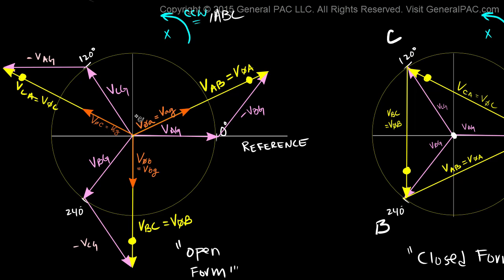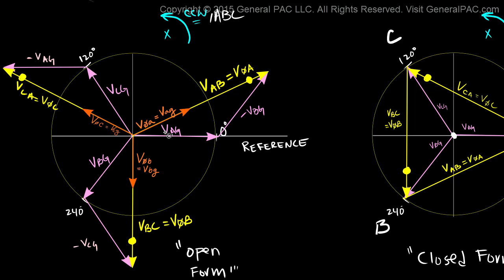In our phasor diagram, we're comparing this VAG — which is the high voltage reference quantity — with VAG on the low voltage side. We're comparing this high voltage reference quantity with this low voltage reference quantity to determine the phase shift. For this transformer connection, it's pretty obvious that the phase shift between the high voltage side and the low voltage side is 30 degrees. The question is how this transformer designation actually works with respect to our phasor diagram.